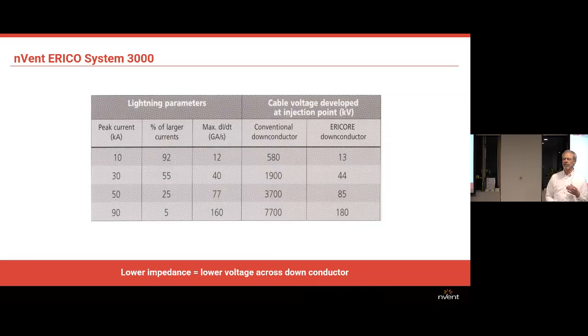And so if you think of lightning as just being a huge current source with no voltage, the voltage is determined by the impedance of your lightning protection system. And so a low impedance cable develops less voltage. There is another supplier of lightning down conductor cable like this out there, and they say that their cable has a high voltage rating. So that's great, but it needs a high voltage rating because it is a higher impedance. Your ideal is to get the minimum impedance possible. So our cable with a lower impedance has a lower voltage rating on it as a result.